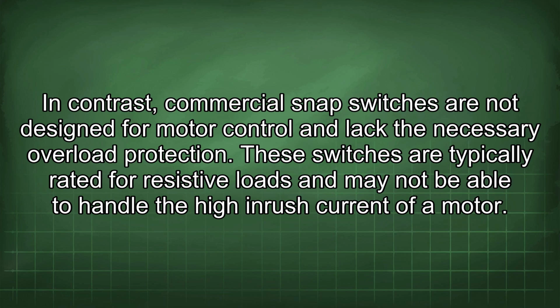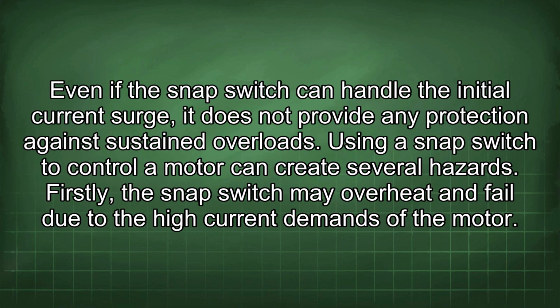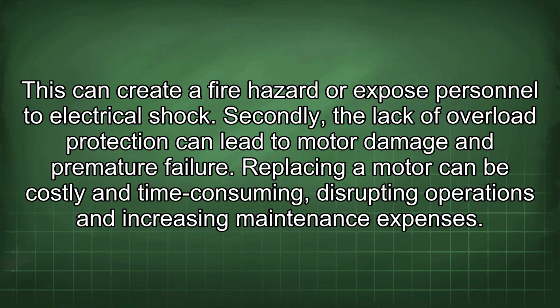These switches are typically rated for resistive loads and may not be able to handle the high inrush current of a motor. Even if the snap switch can handle the initial current surge, it does not provide any protection against sustained overloads. Using a snap switch to control a motor can create several hazards. Firstly, the snap switch may overheat and fail due to the high current demands of the motor. This can create a fire hazard or expose personnel to electrical shock. Secondly, the lack of overload protection can lead to motor damage and premature failure. Replacing a motor can be costly and time-consuming, disrupting operations and increasing maintenance expenses.